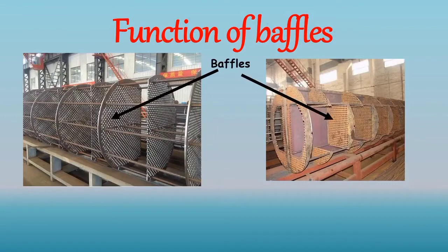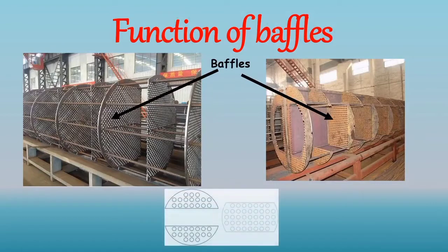In the heat exchanger, baffles must overlap at least one tube row in order to provide adequate tube support. And they should be spaced evenly throughout the tube bundle to provide even fluid velocity and pressure drop at each baffle tube section.